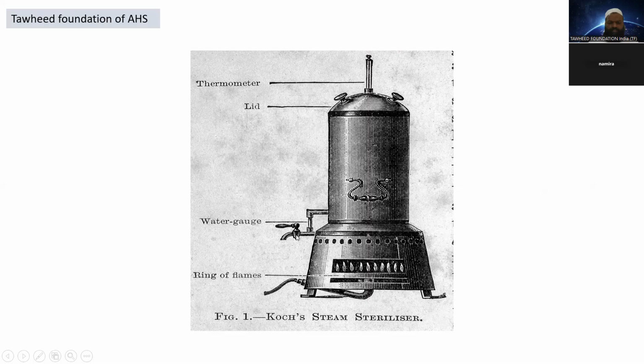Koch steam sterilizer was one of the earliest devices for sterilizing laboratory and medical instruments using moist heat steam. This diagram shows the main components and their functions, representing a significant milestone in the history of microbiology and aseptic techniques. We'll start with the thermometer. The thermometer measures the internal temperature of the sterilizer. Its function is to ensure that the water inside reaches the required temperature, typically above 100 degrees Celsius, for effective sterilization. The thermometer is usually inserted through the lid at the top of this container.